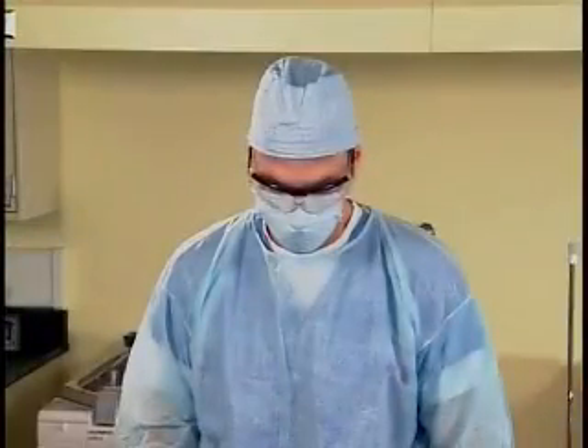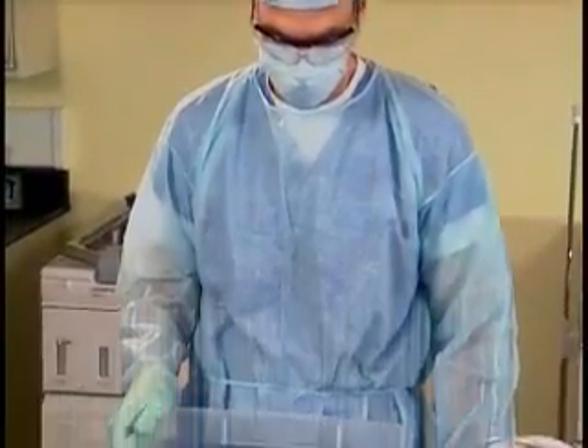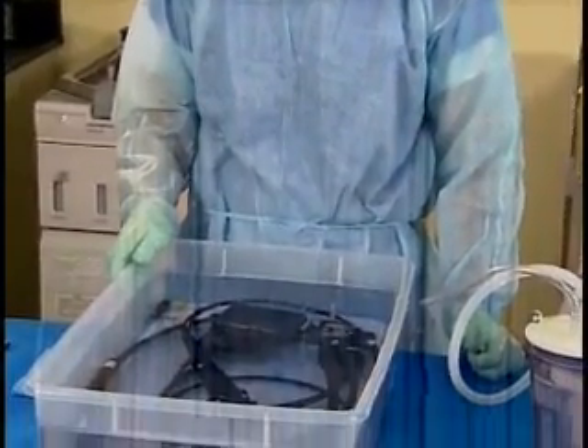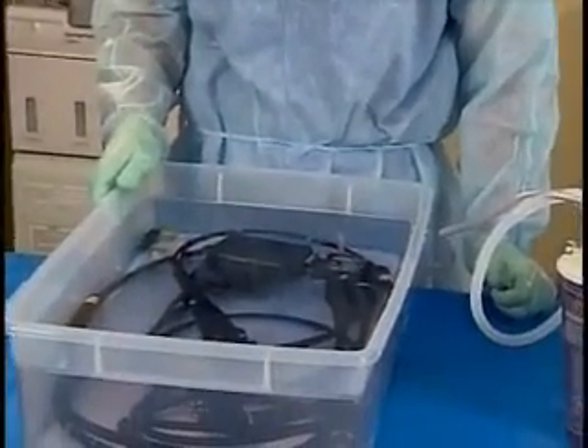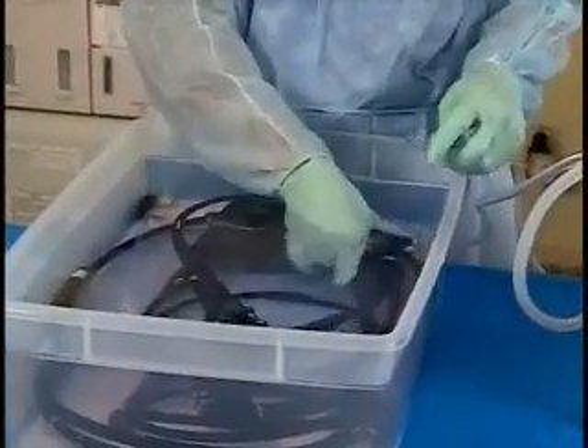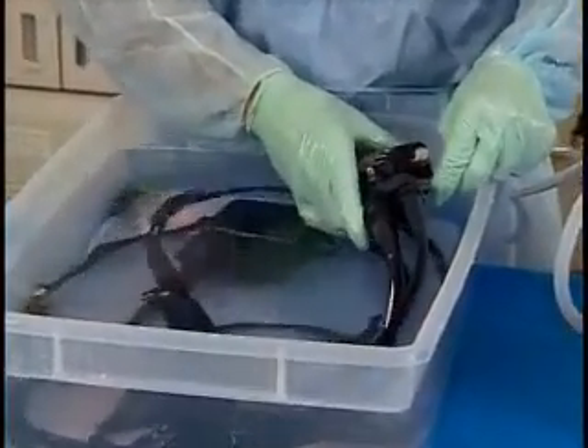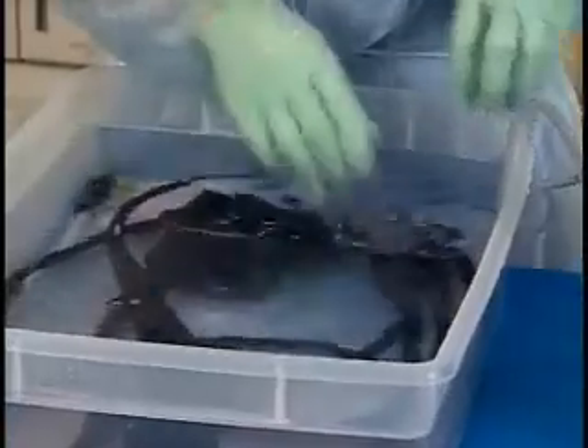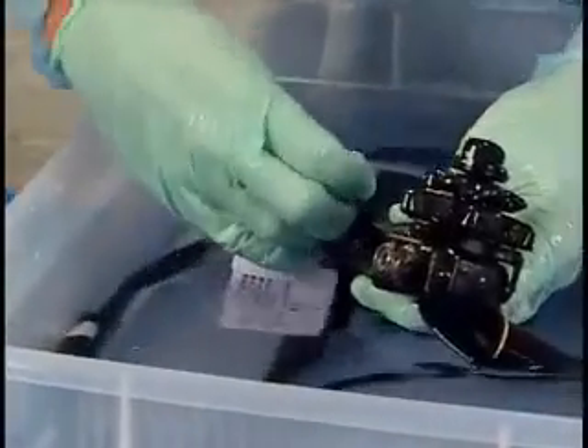Now that the channels have been brushed, the next step is to flush the channels with detergent solution to remove any remaining debris. Connect the endoscope to a source of suction. Attach the adapter and suction cleaning tube to the instrument port.